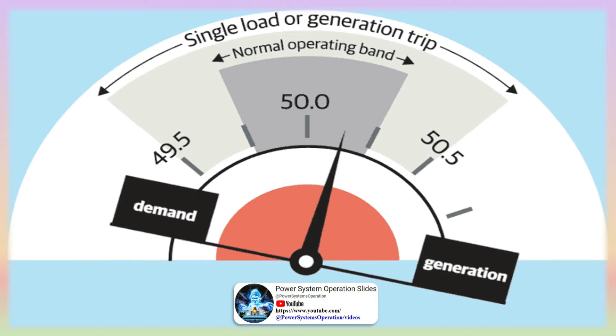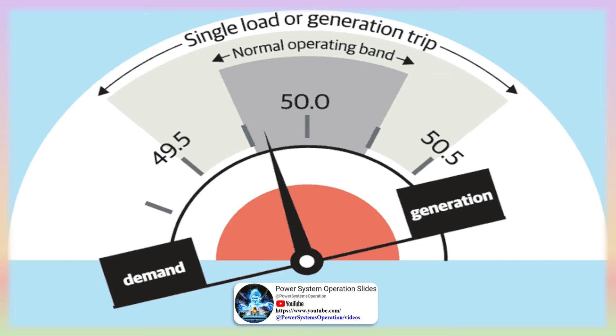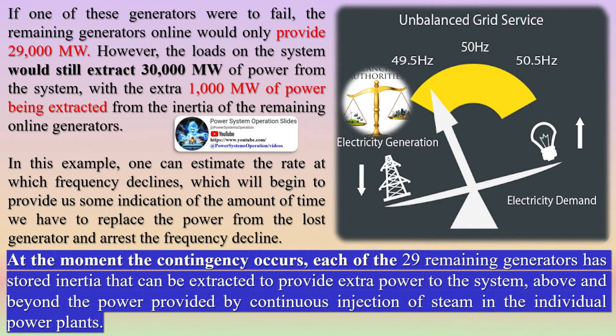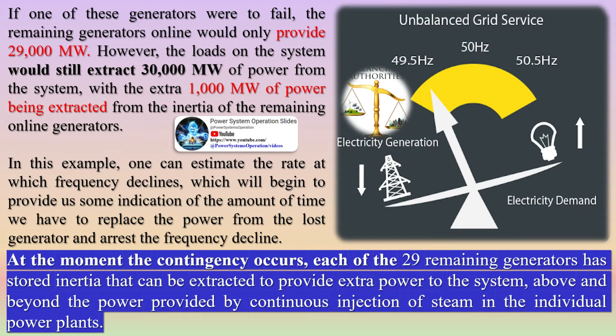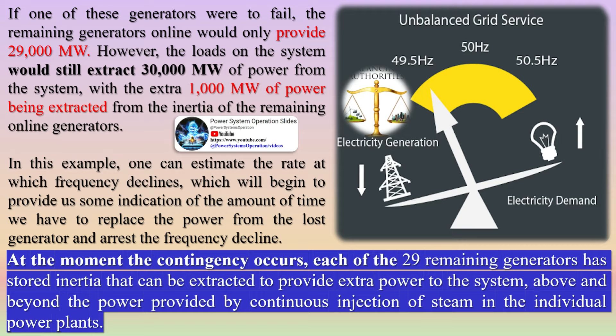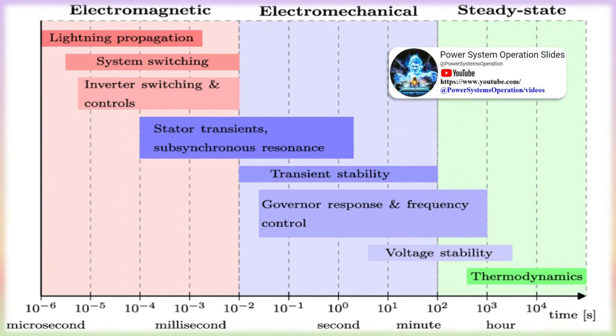The extra 1,000 MW would be extracted from the inertia of the remaining online generators. One can estimate the rate at which frequency declines, providing some indication of the time available to replace the power from the lost generator and arrest the frequency decline. Assuming the generators are all identical, each must provide an extra 34 MW from stored energy (1,000 MW divided by 29 generators). The constant injection of energy from fuel provides 1,000 MW and 34 MW is drawn from stored energy, meaning each generator is providing 1,034 MW.